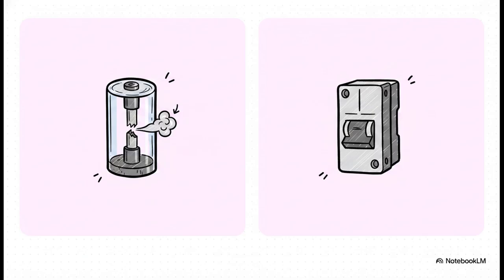Luckily, inside your house, we stop this using vaporizing fuses or tripping circuit breakers. A fuse uses a thin piece of foil that physically vaporizes to instantly kill the current during an overload. Circuit breakers use the heat of the overload to mechanically trip a switch, which is why you can just pop down to your basement and reset them.